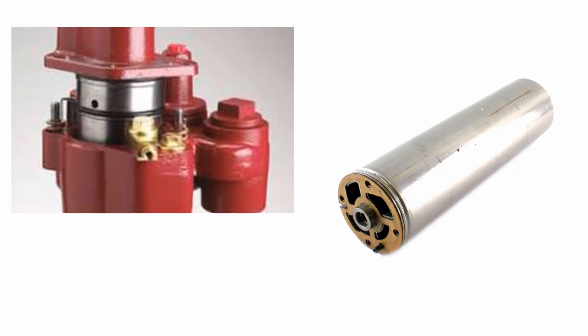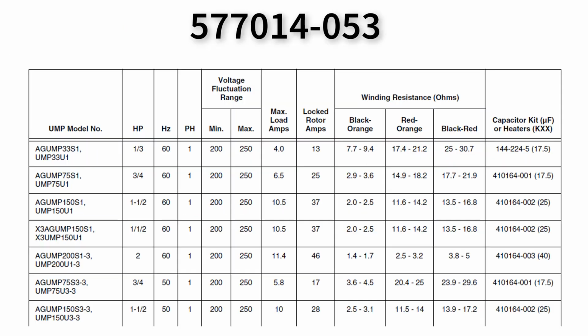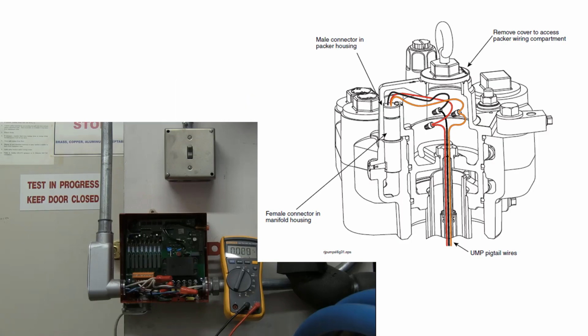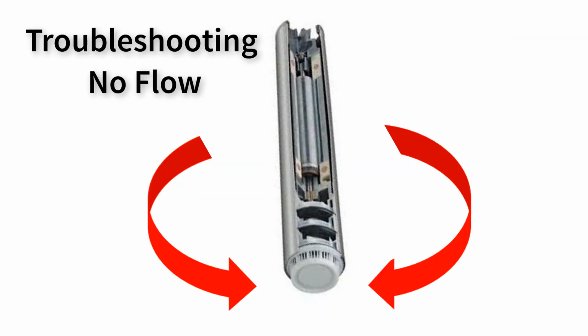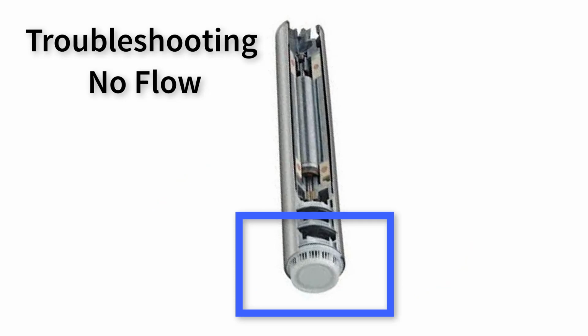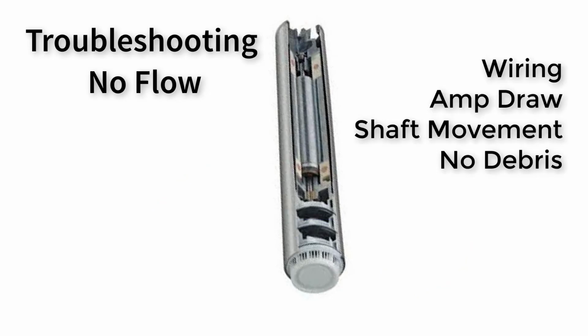If the current reading is out of range, reference 577-014-053, Electrical Service Information. Verify all the wires are tight. Verify the UMP shaft spins freely. Make sure there is no debris at the intake of the UMP. If wiring, amp draw, and shaft movement are within normal range and there is no debris, replace the UMP.